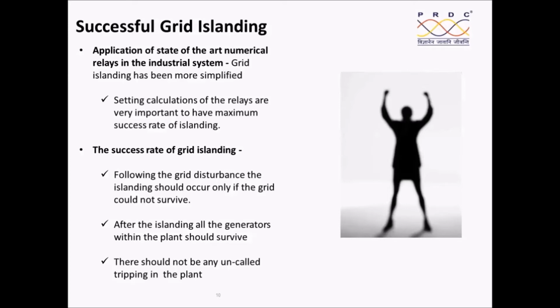If a process motor, which is very, very vital, trips because of the grid disturbance and there is a low voltage, there can be a cascaded tripping. Therefore, even though you have successfully islanded some other motor, auxiliary in the auxiliary power plant, some other motor may trip, and it may so happen that the entire plant may collapse. Therefore, it is not just your electrical system. We also need to see the behavior of your process systems. So one important process which has an interconnection with your captive power plant should not trip. If it trips, it may so happen that even with successful islanding, the entire CPP may come down. Therefore, that is very, very important for us to understand.